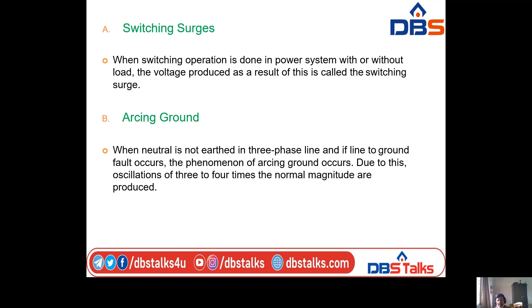What is meant by arcing ground? When the neutral is not earthed in a three-phase line and a line to ground fault occurs, the phenomenon of arcing ground occurs. Due to this, oscillations of three to four times the normal magnitude are produced. That may give rise to transients.